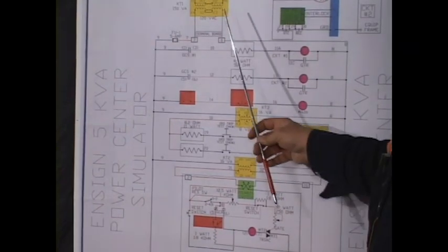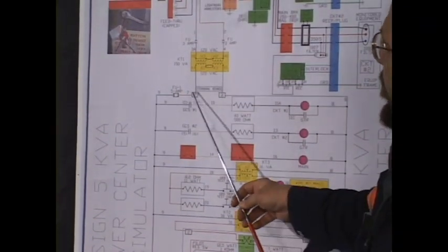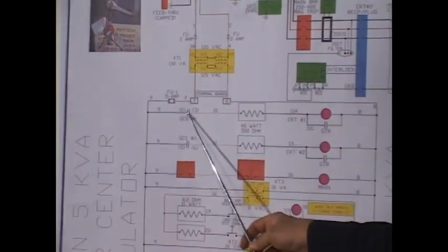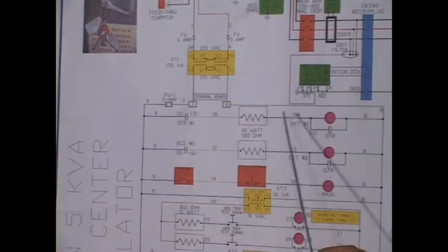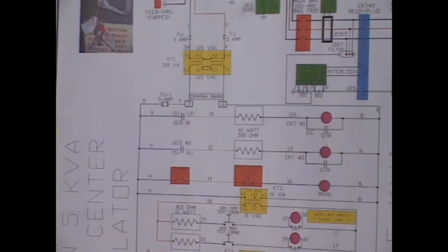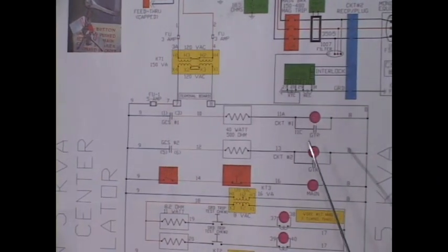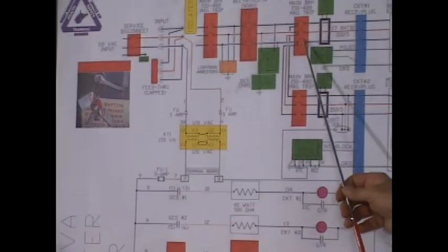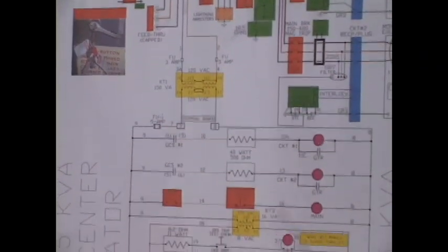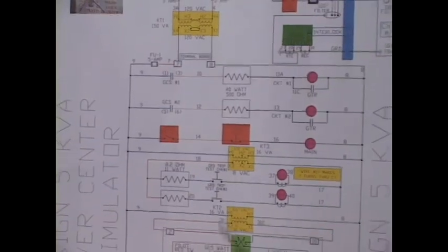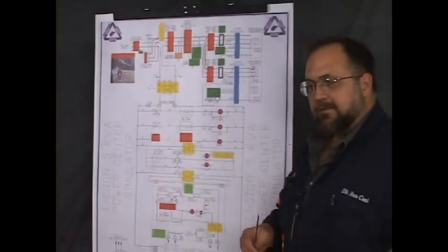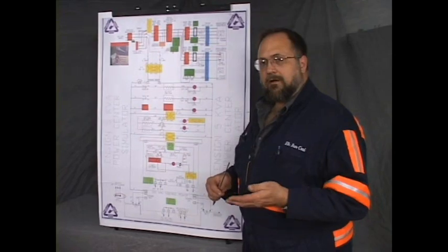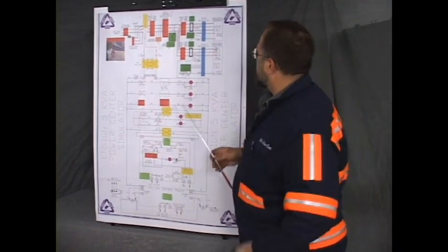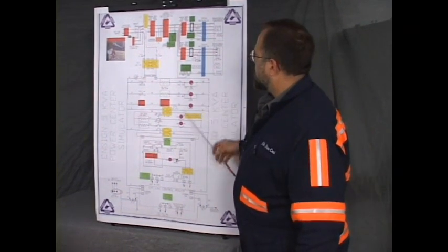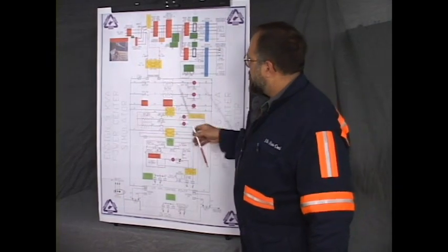Now, all right, our problem, if you could see it on the print, we have control power. The monitor appears to be closing, but the breaker won't set. The UVR is not becoming energized. It's not allowing this breaker to be closed. The UVR is more or less a trigger. When it's energized, it makes a magnet, lifts a linkage up off of a trip mechanism in the breaker. And that's not happening. It's not closing. Contacts are closed, no power here.